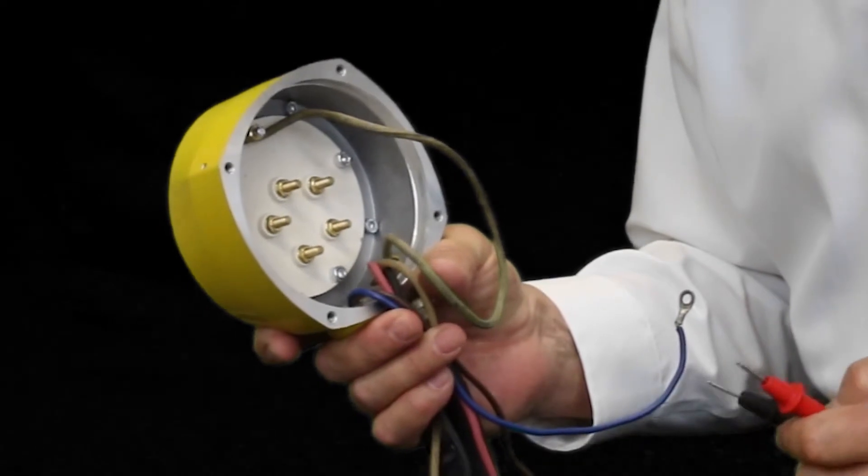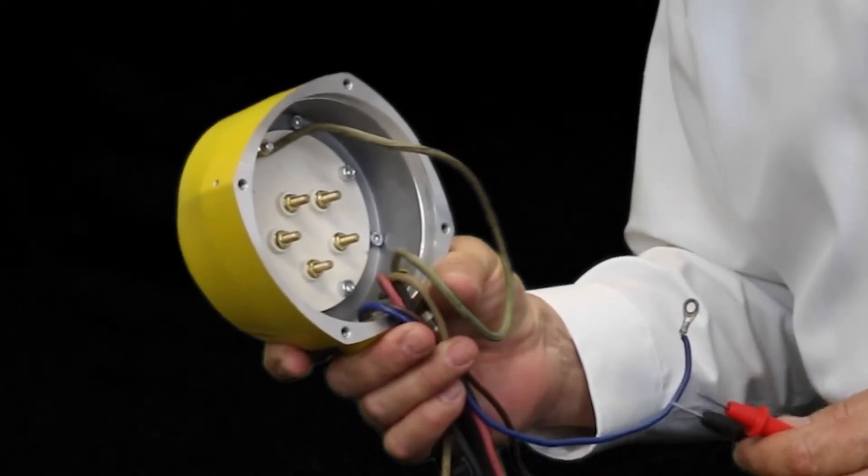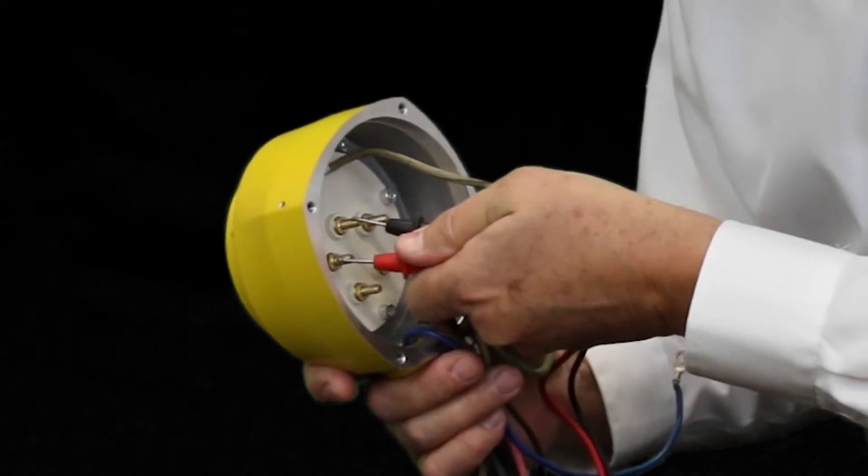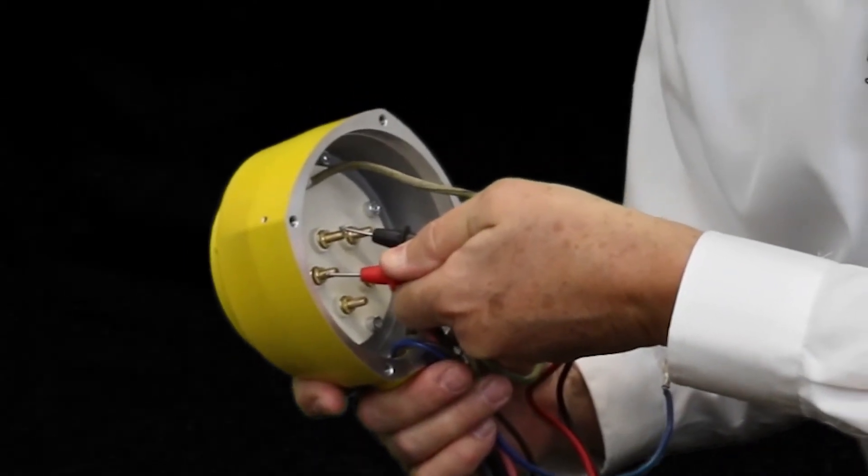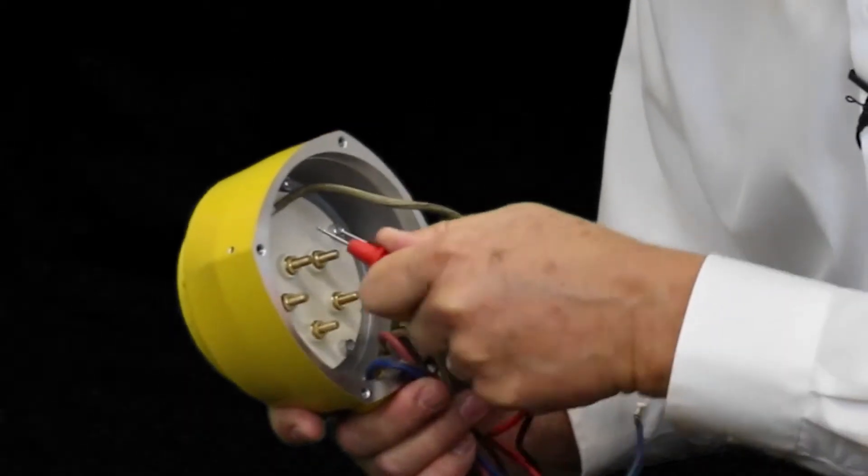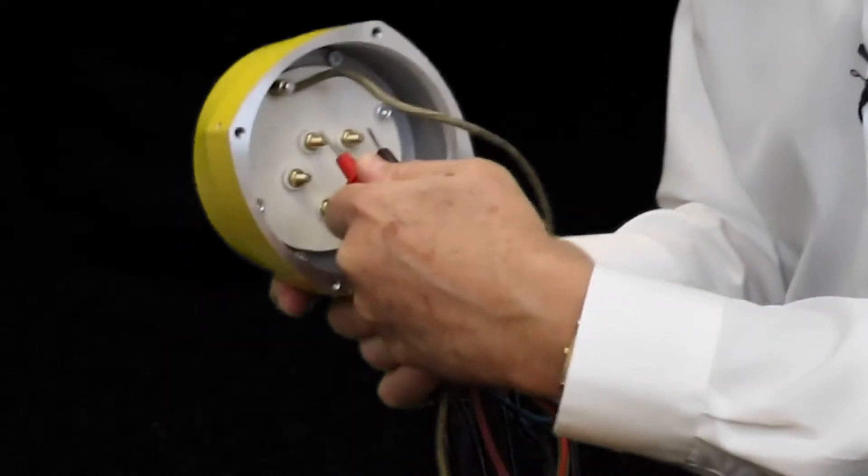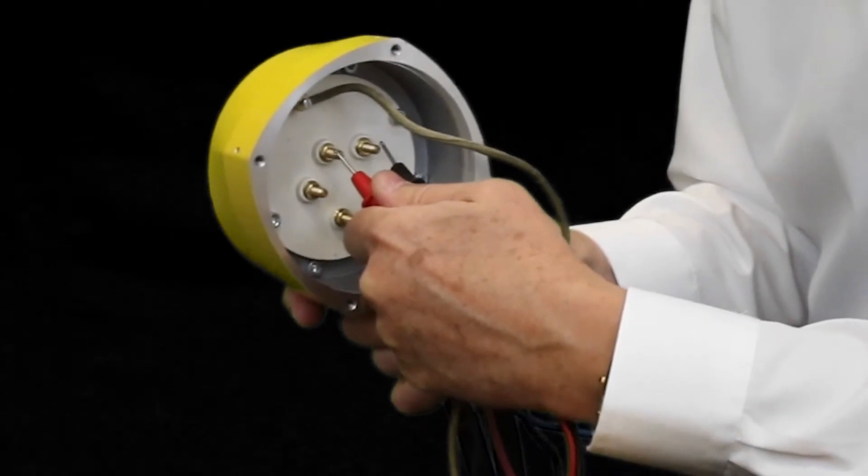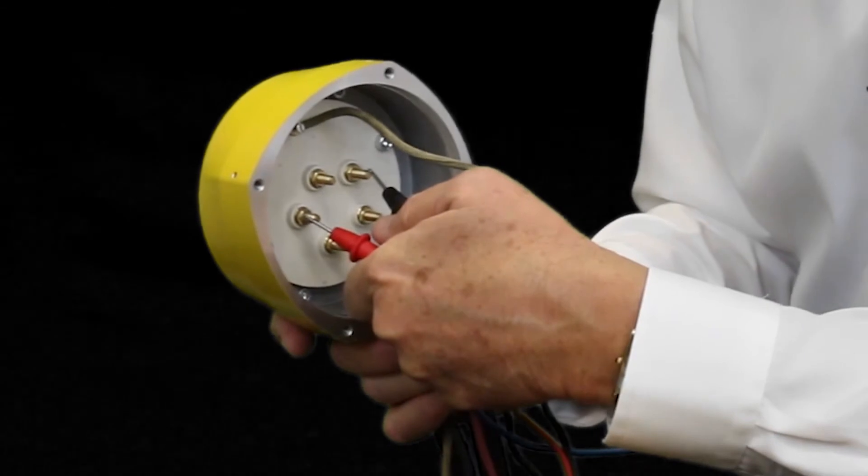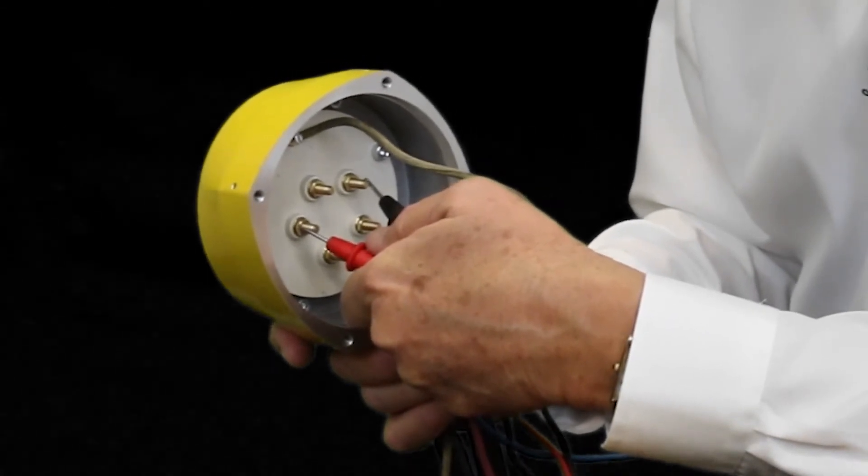We set the probes between U and V to check the resistance in phase one. V and W to check the resistance in phase two. And U and W to check the resistance in phase three.